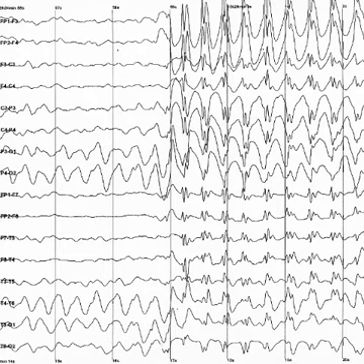The digital EEG signal is stored electronically and can be filtered for display. Typical settings for the high-pass filter and a low-pass filter are 0.5 to 1 Hz and 35 to 70 Hz respectively. The high-pass filter typically filters out slow artifact, such as electrogalvanic signals and movement artifact, whereas the low-pass filter filters out high-frequency artifacts, such as electromyographic signals. An additional notch filter is typically used to remove artifact caused by electrical power lines, 60 Hz in the United States and 50 Hz in many other countries. The EEG signals can be captured with open-source hardware such as OpenBCI and the signal can be processed by freely available EEG software such as EEGLAB or the Neurophysiological Biomarker Toolbox.